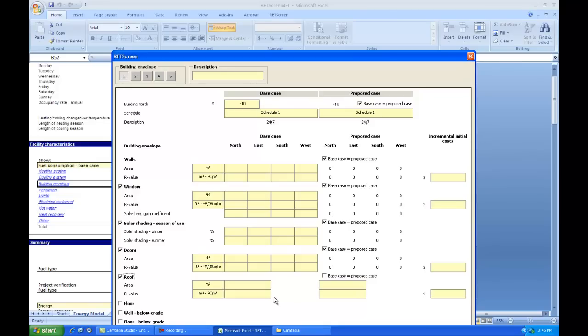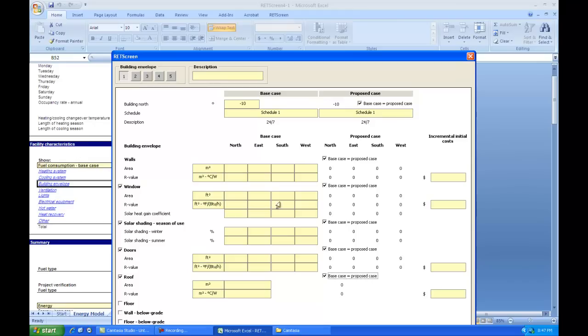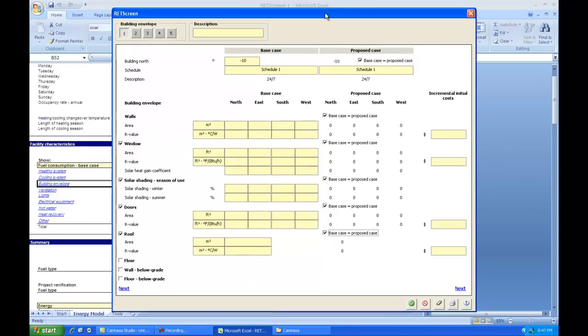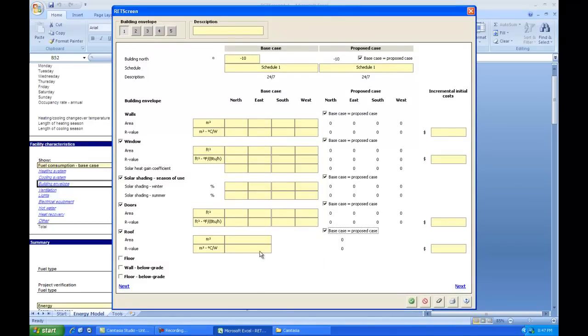But normally the ceiling, that is a flat ceiling, will be the thermal boundary of our building. And we would enter the area of that here and the R value of that here. Notice that we don't care what direction the ceiling faces because it doesn't experience any sunlight. The direction matters on all of these other things because the sun can shine on them. And RETScreen will take the effect of that into consideration when it figures out our heat loss.